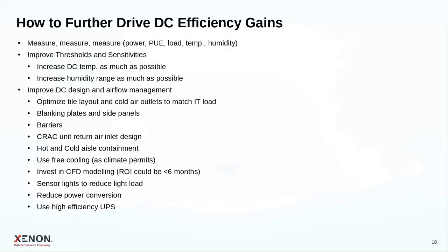A lot of that also has to do with hotspots in the data center, where you need to make sure that even in the hottest area you have enough cooling so your systems don't overheat. This really comes down to the data center design, optimizing the tile layout and air outlets to match the IT load and exactly avoid those hotspots.